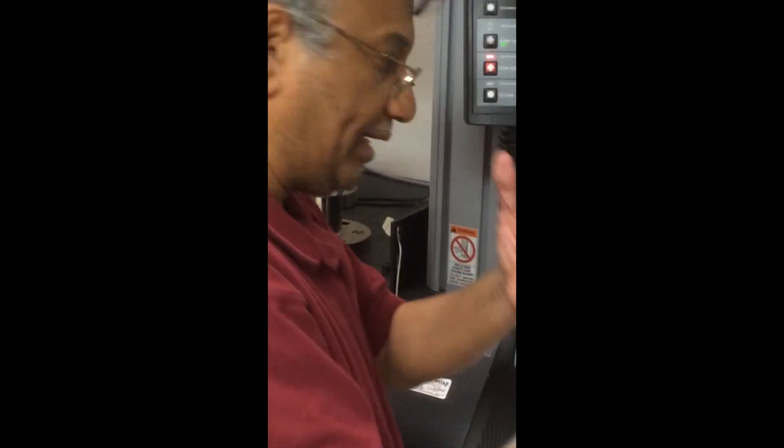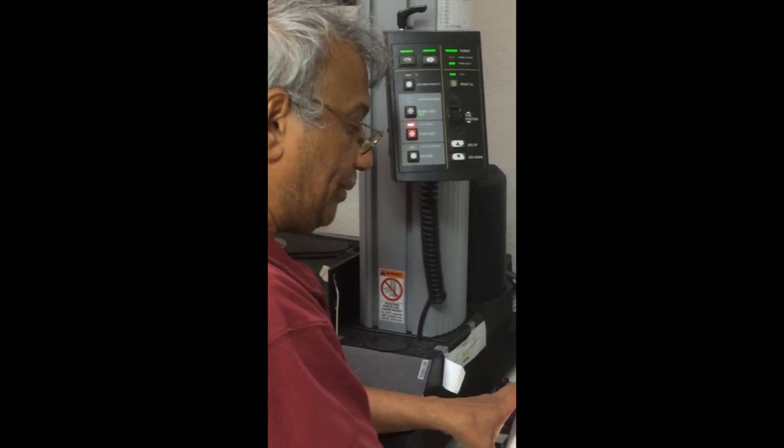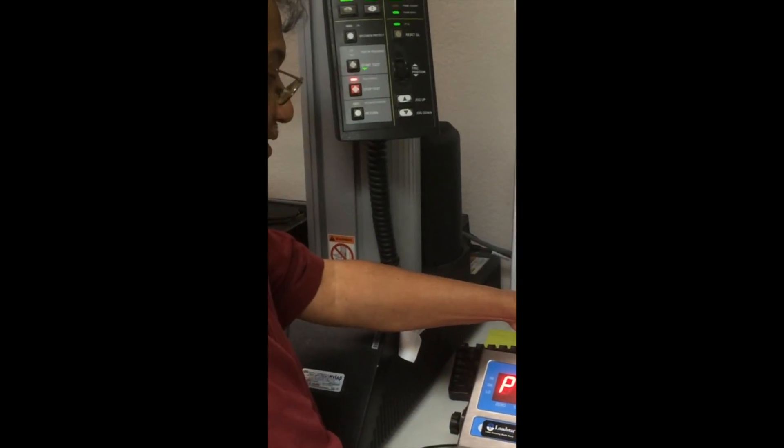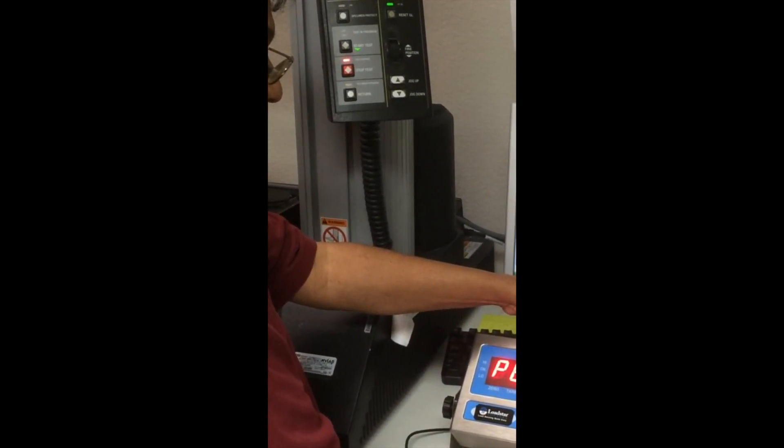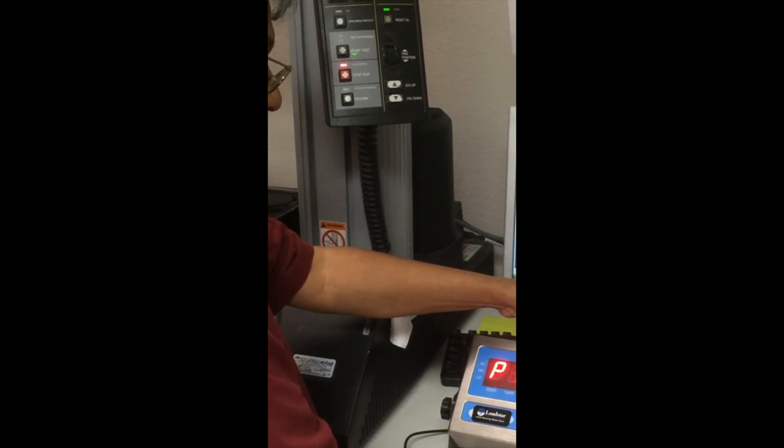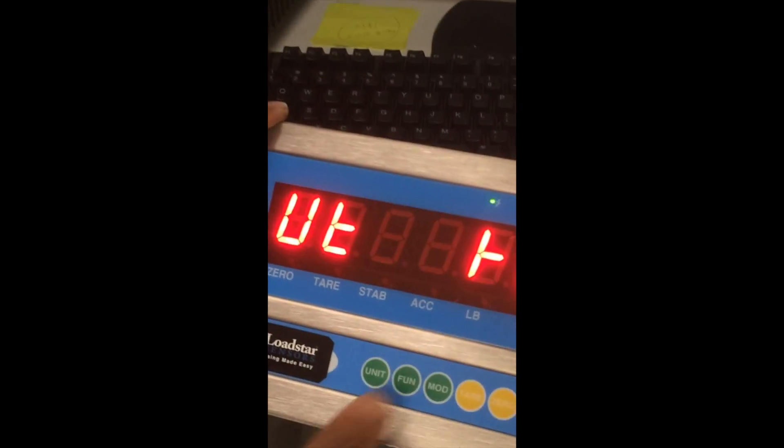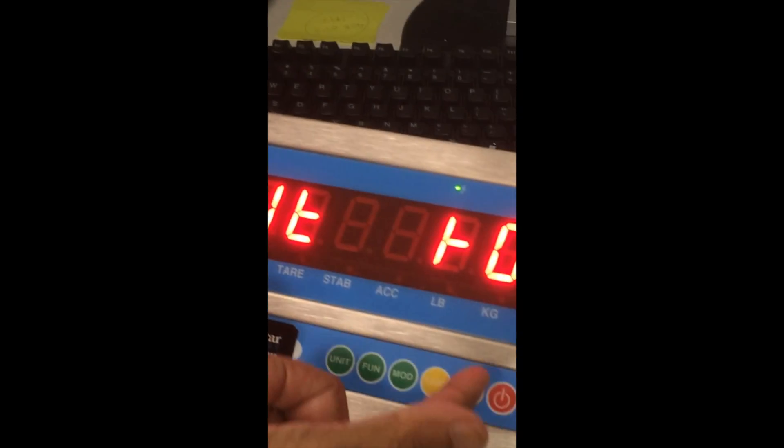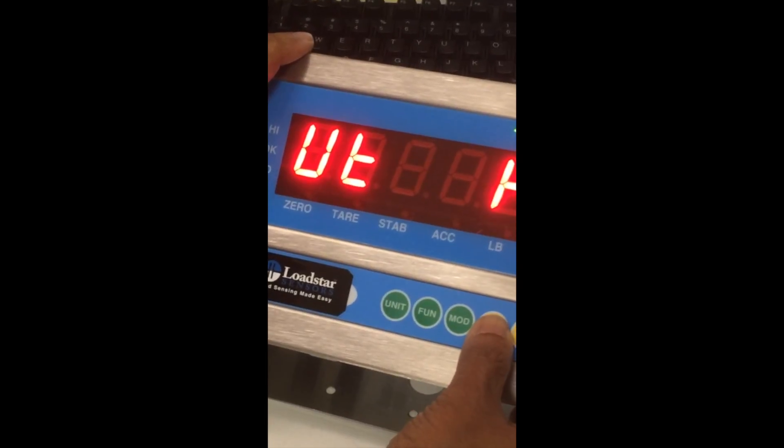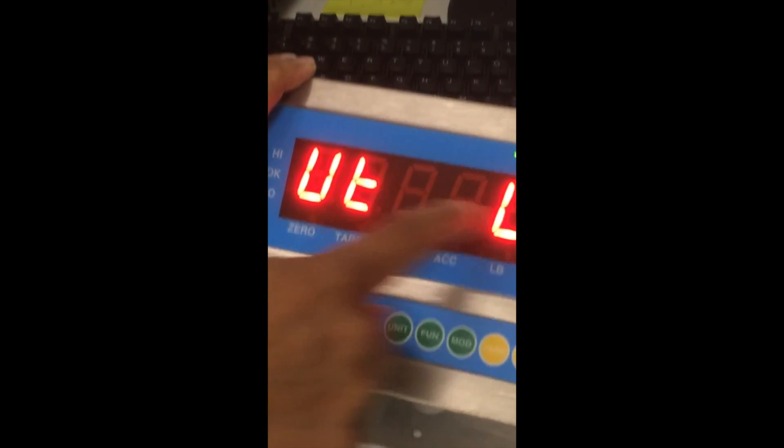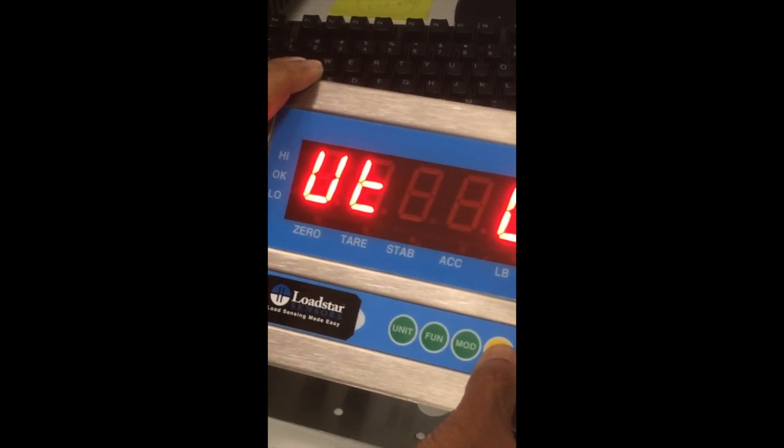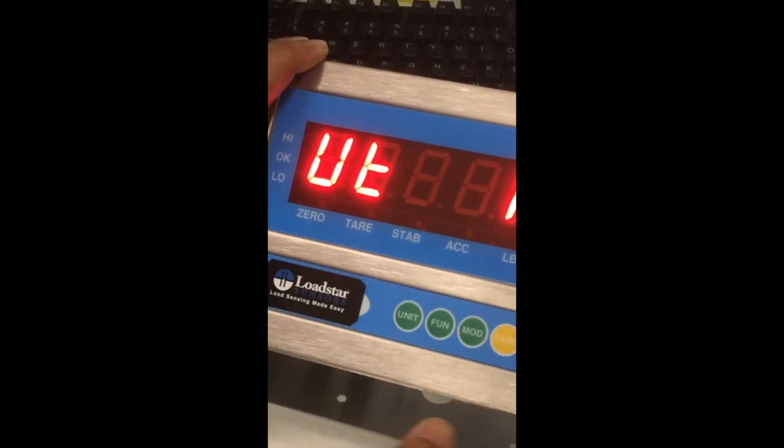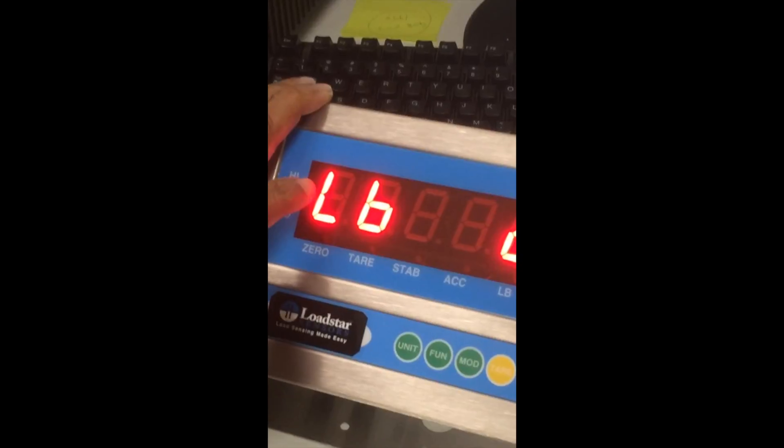So you come to another set of menus P1 through PXX. So keep going up till you see UT for units. Here P13. Press the function key and the unit is set in kilograms. If it is set in pounds, you will see something like this, unit pounds. So change it back to kilograms using the tare key and then press function to enter it, accept it.